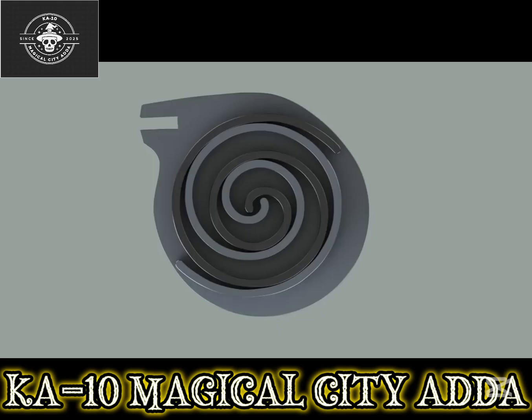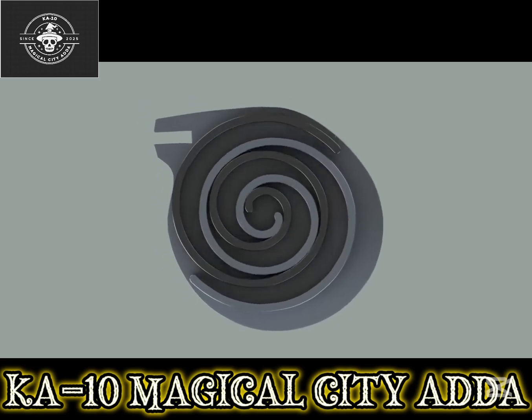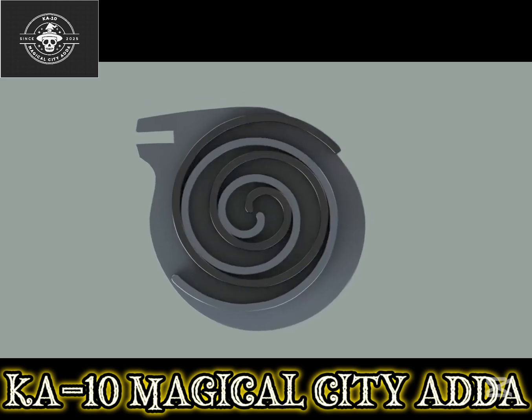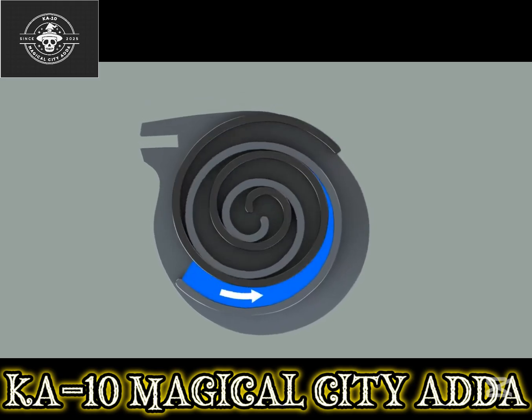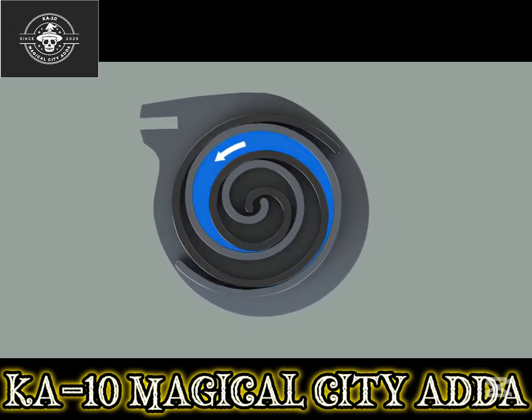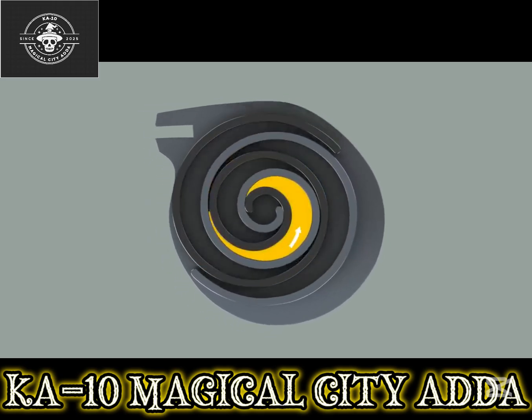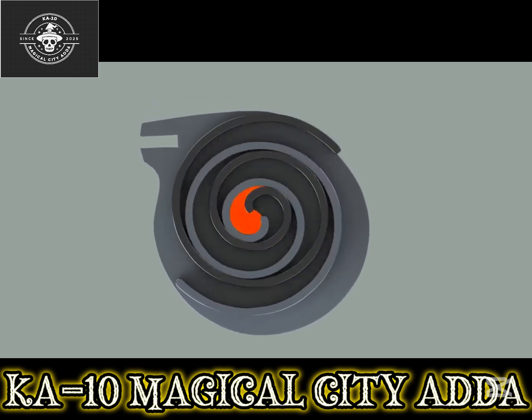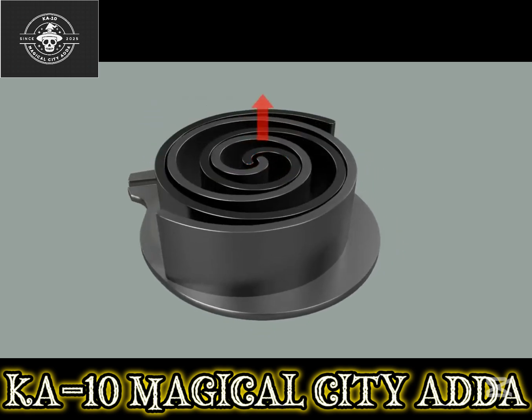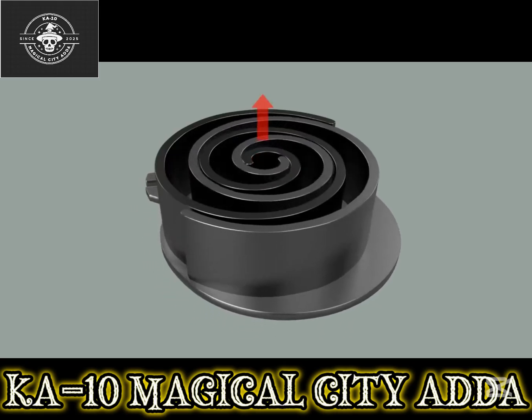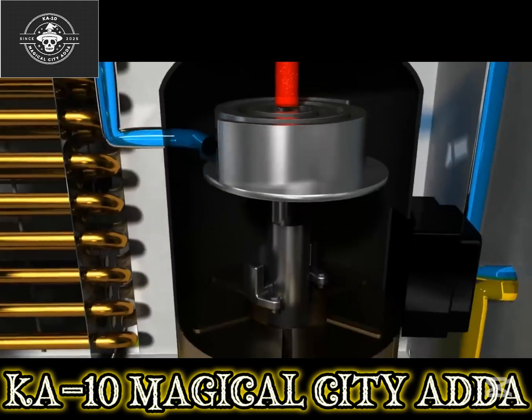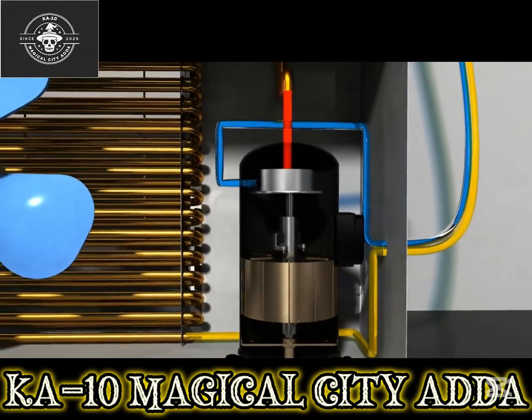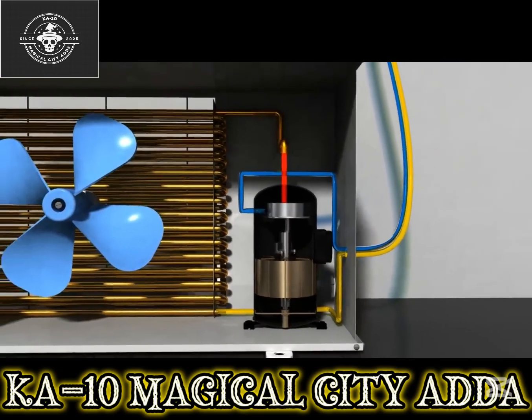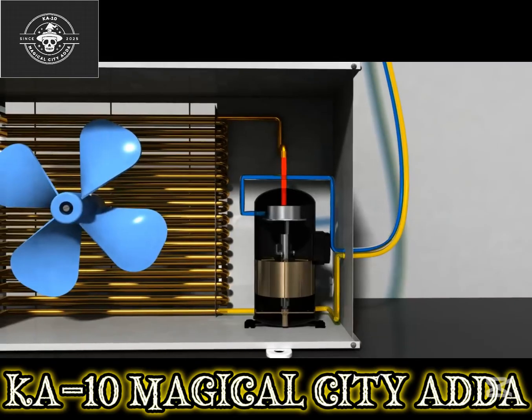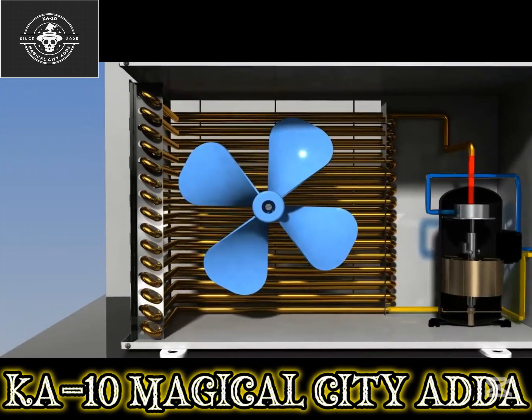In a scroll compressor, there are two scrolls of which one is fixed and the other rolls constantly. As more air coming through the entrance gets inside the scroll, space becomes crowded. As there is less space now, gas becomes more compressed and is discharged from the middle of the scroll in a compressed state. The reason for using such a type of compressor is the efficiency of space utilization. This type of compressor allows the machinery to become smaller in size and reduces noise as well as vibration. Compressed gas is then sent to a condenser to be pressed into liquid.